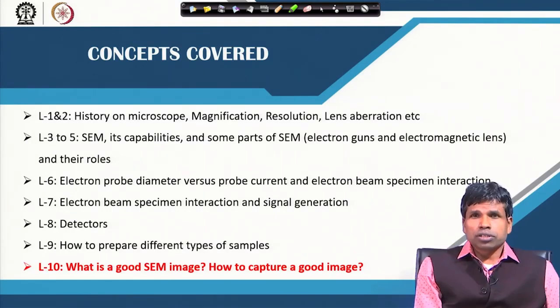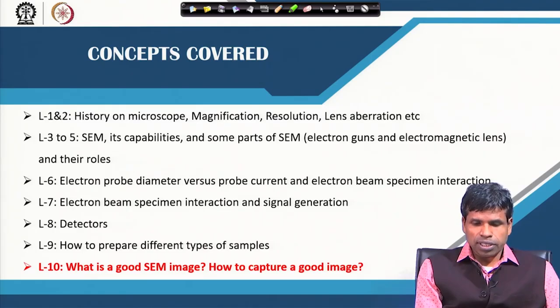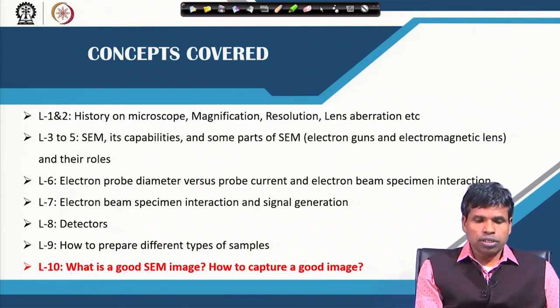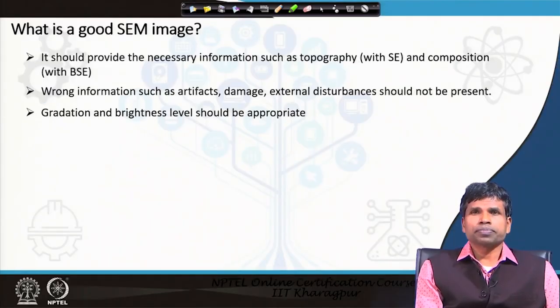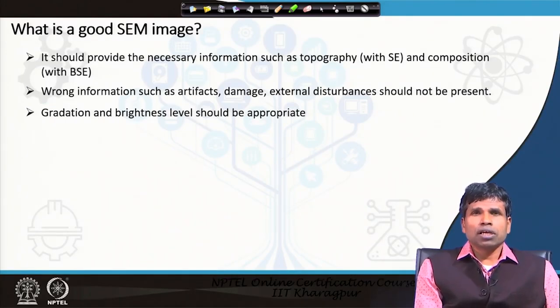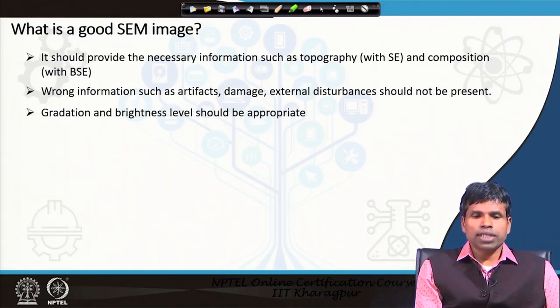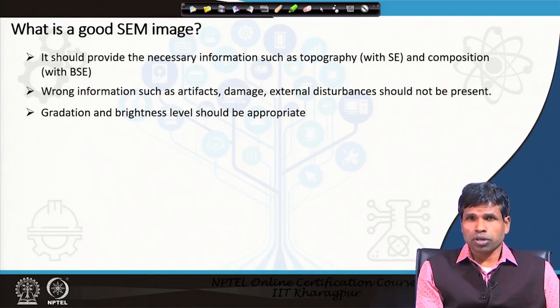We will discuss what is a good SEM image and how to capture a good SEM image, after discussing the preparation of different types of samples for SEM. A good SEM image is one that provides us the necessary information such as topography and surface morphology.